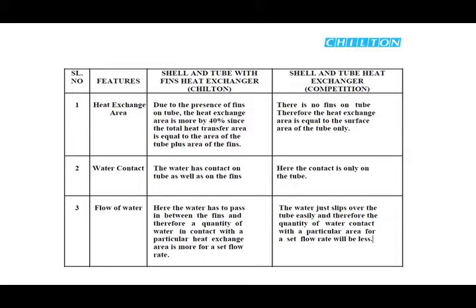Water contact, Chilton: the water has contact on the tube as well as on the fins. Competitor: here the contact is only on the tube. Flow of water, Chilton: here the water has to pass in between the fins and therefore the quantity of water in contact with a particular heat exchange area is more for the set flow rate. Competitor: the water just slips over the tube easily and therefore the quantity of water in contact with a particular area for a set flow rate will be less.